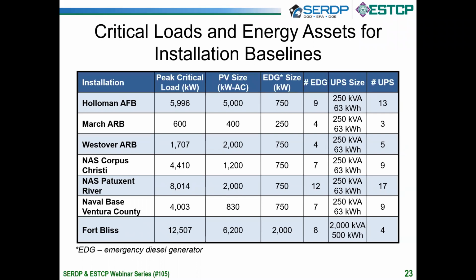For each of these installations, we then defined the baseline diesel-only microgrid. For each installation, we selected a size for these generators. They range from 250 kW up to 2 megawatts. That size was selected based on engineering judgment and standard practice used in the industry. Then the microgrid was configured to ensure it had an N+1 reliability. By that I mean we selected the number of generators to be 1 more than would be necessary to meet the peak critical load. And those values range from 4 for the very small reserve bases to up to 12 for Pax River.